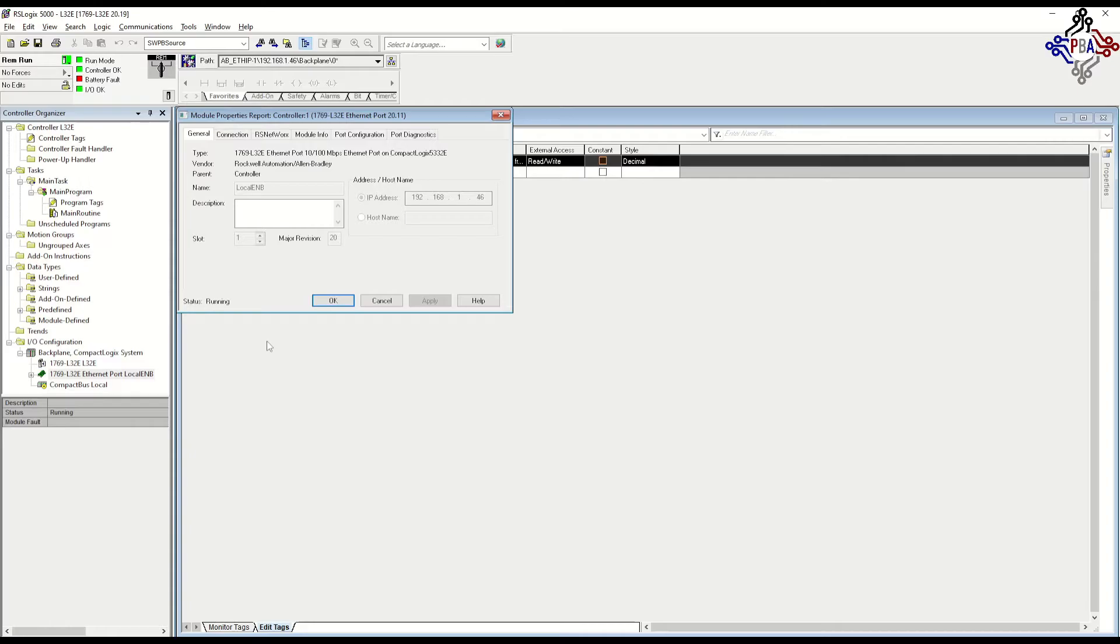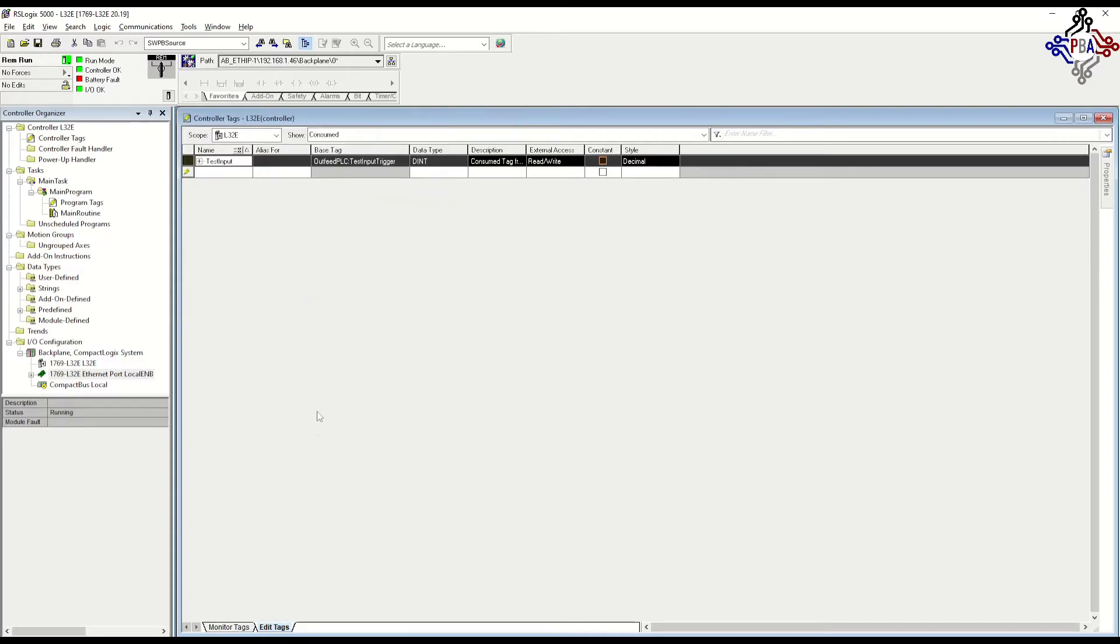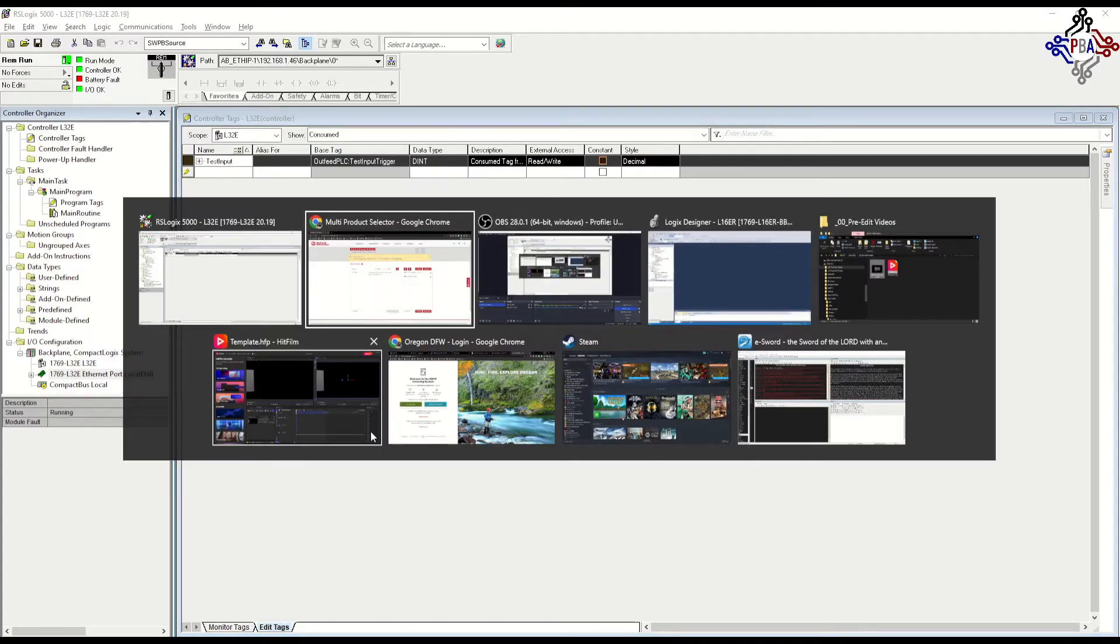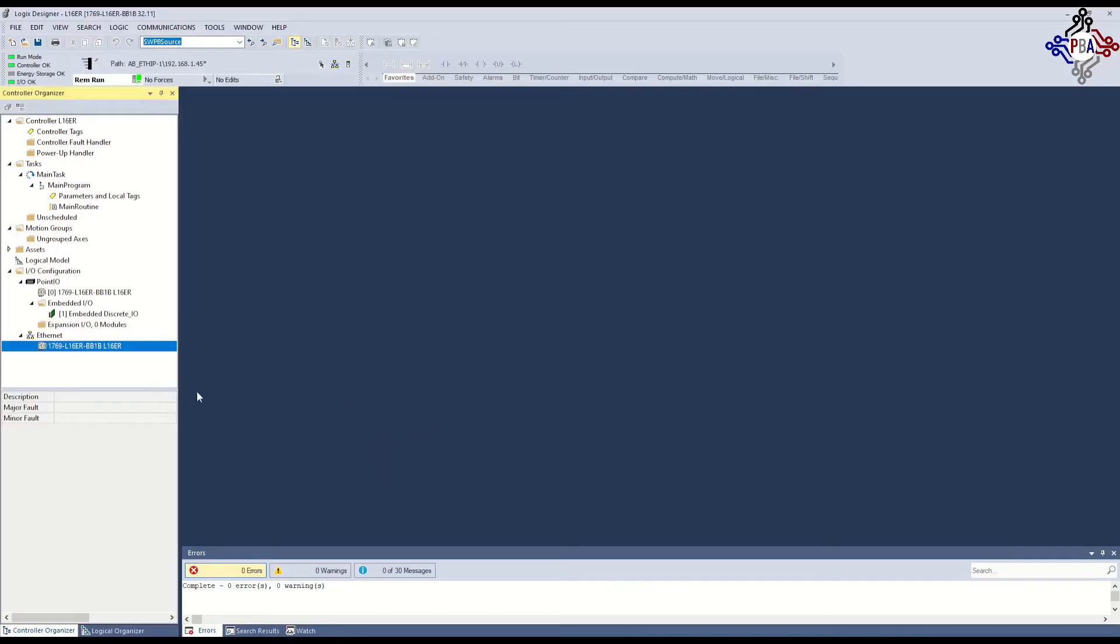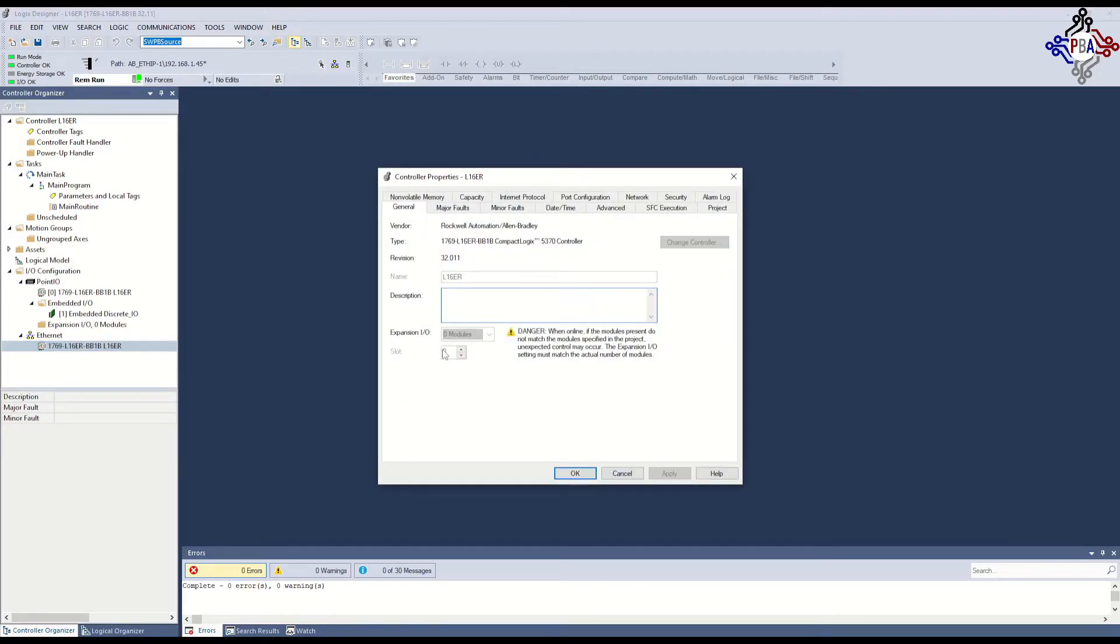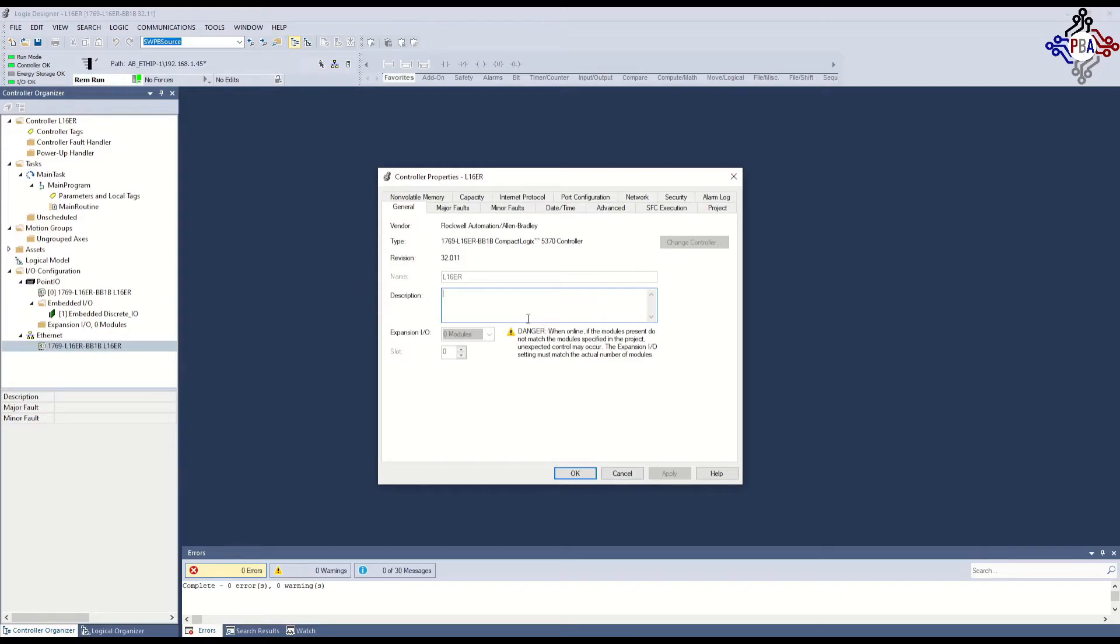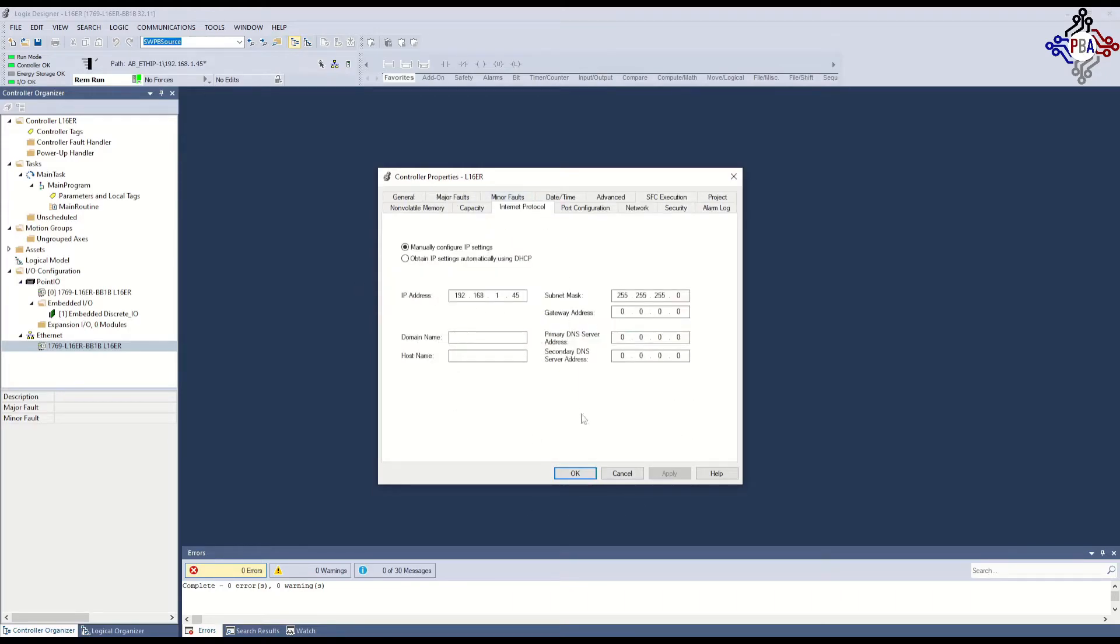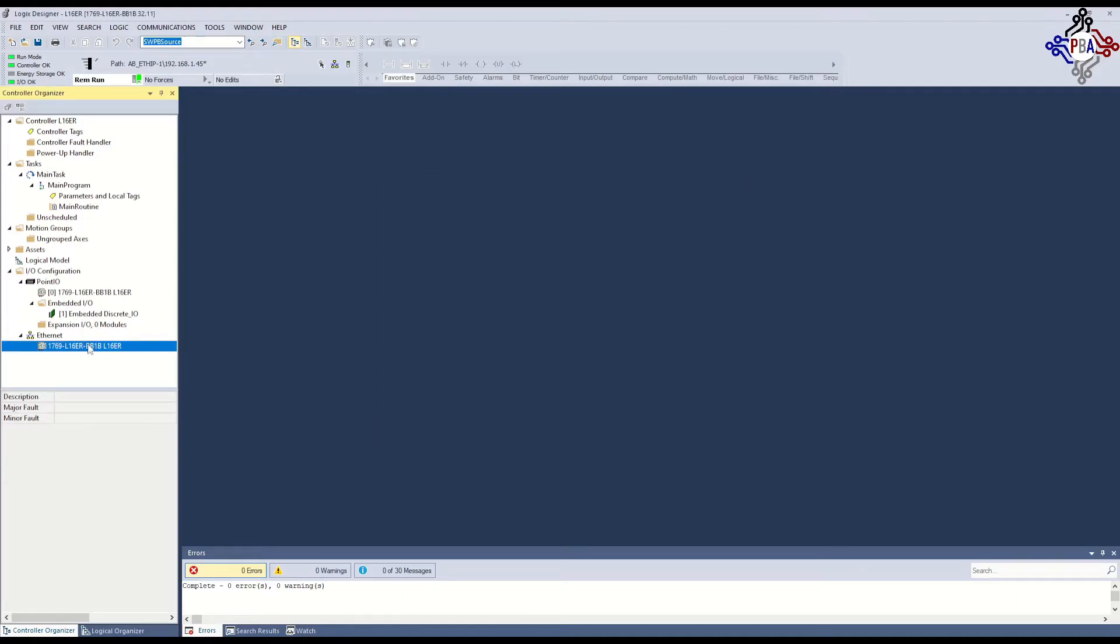This is a little different than if we go over here to Studio 5000. You can see we've got in slot 1 our controller, but the Ethernet card is integrated to the controller. It's a part of it. It's onboard. The Internet protocol is inside the controller, so we don't have the Ethernet in slot 1. So when we add modules on the side of it, you'll end up with slot 2 is module number 2.